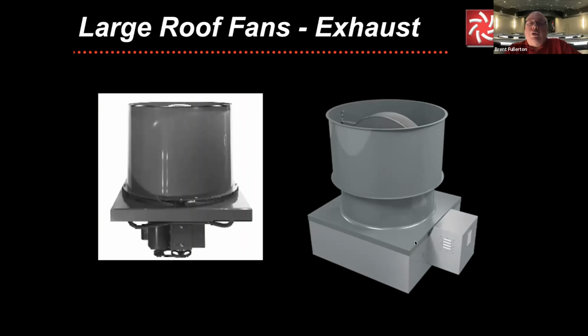Additionally, if you have a pressure differential go through because of a storm or wind or anything along those lines, the path of least resistance to get the pressure equalized in a building can come into play. So the butterfly dampers, even if they have magnetic latches trying to hold that down, it can pop those things open. Now they'll come back down once the pressure is equalized, or they can shatter. But this is one of the most frequent cons of this style of product, but they are very, very cost-effective styles of products as well.